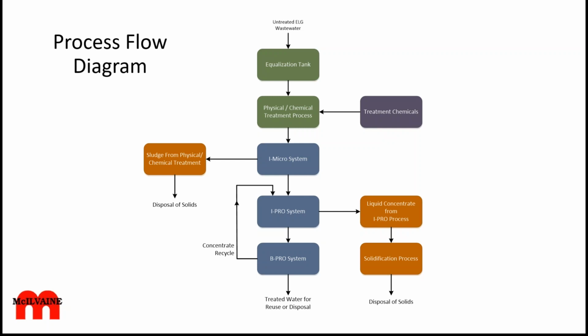So it's a delicate balance, is it not? It is. But having the monitoring system and some triggers, if you see a change in the transmembrane pressure, it can trigger an automatic clean in place of the system. And if that happens more frequently than typical, it may have to go into a membrane replacement, which is typically on an annual basis or every 6 months.